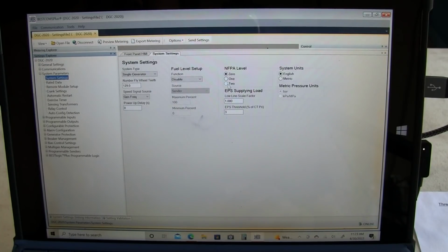Level 2 would be anything like a pump station for a sewer plant, or maybe a backup generator for a manufacturing facility, as long as there was no life safety equipment on it like exit signs and egress lighting. Let's see. System units English, or for our Imperial. And speed signal source, gen frequency. It can also be mag pickup frequency. We're using gen frequency. I usually set them to use gen frequency just so you don't have to have a second mag pickup for the controller.